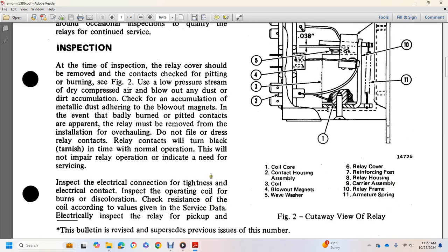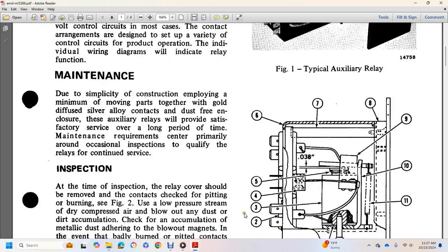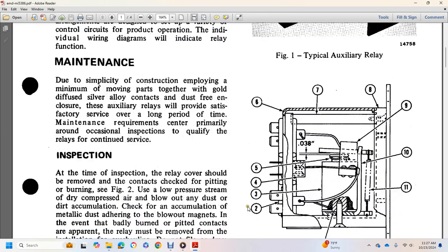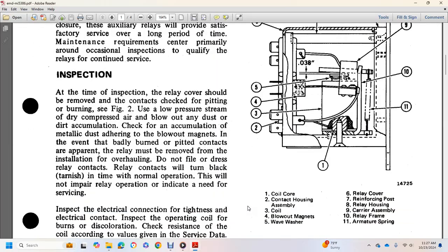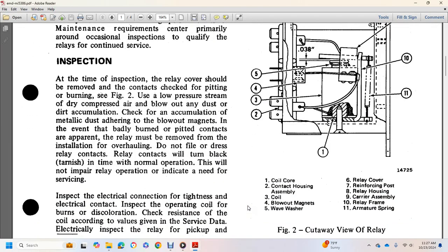Inspect electrical connections for tightness of electrical contact. Inspect the operating coil for burn or discoloration. Check the resistance of the coil according to the values given in the service data. Electrically inspect the relay for pickup. Figure 1 shows the typical auxiliary relay. Figure 2 shows a cutaway view of the relay.